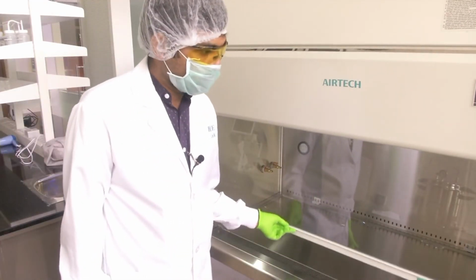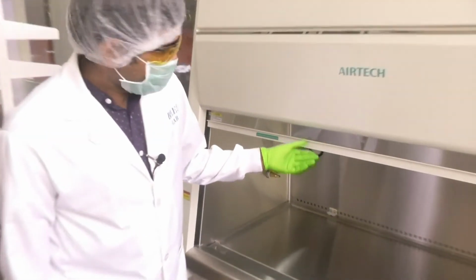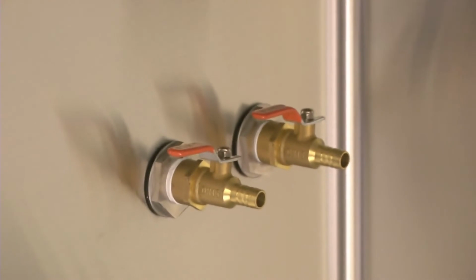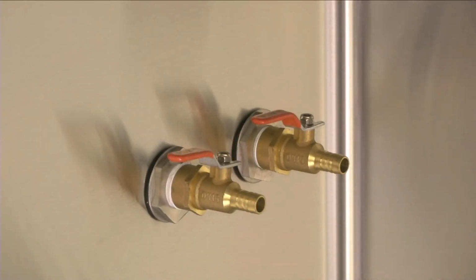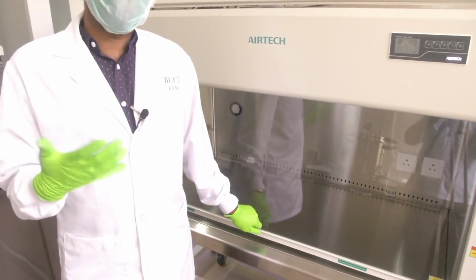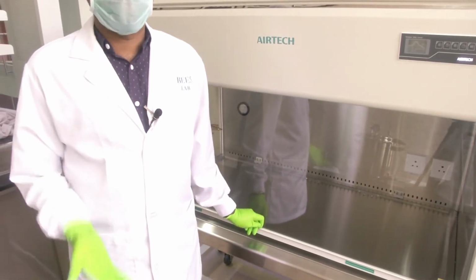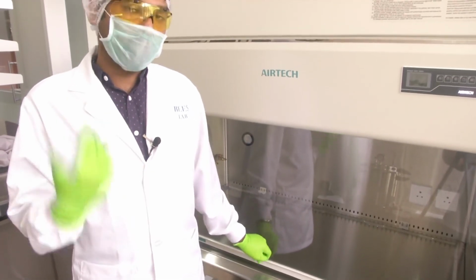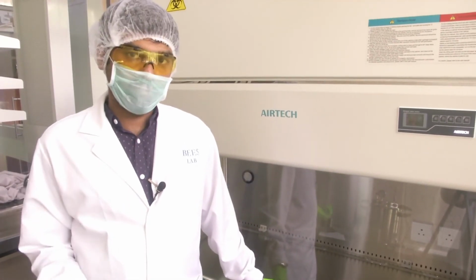So, I will just lift it now. There are 2 nozzles. These nozzles can be used to supply deionized water or distilled water, very clear water, and also to circulate air inside the biosafety cabinet. Now, in a class 1 biosafety cabinet, as I told, there is no product protection provided. What it means is that the air that comes in contact with the sample might not necessarily be free of contaminants. What it also means is that you will just be circulating normal air within your cabinet. So, that is class 1.